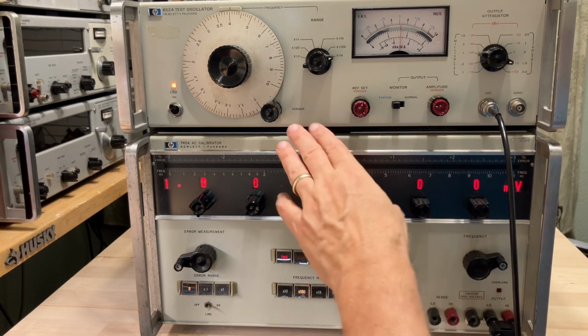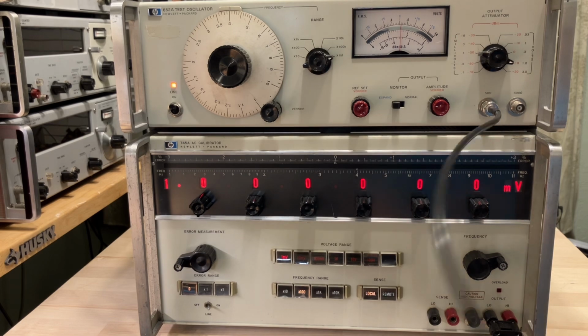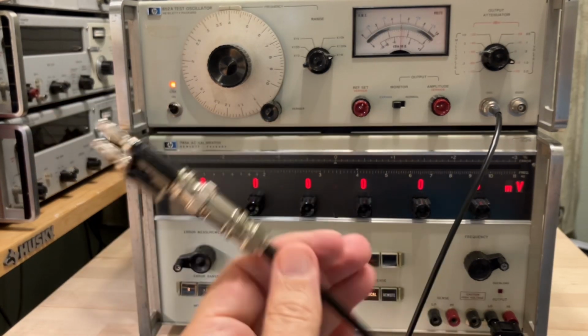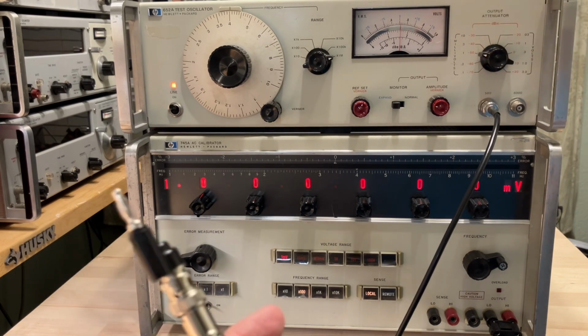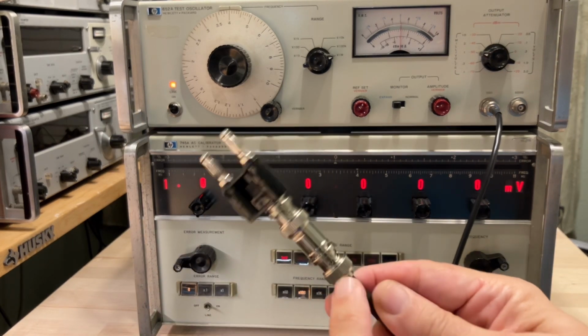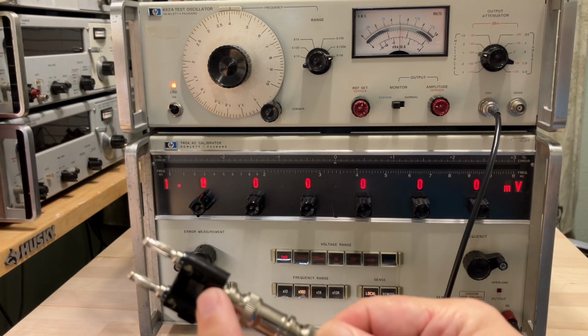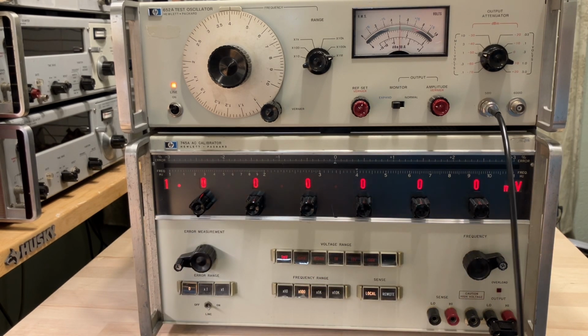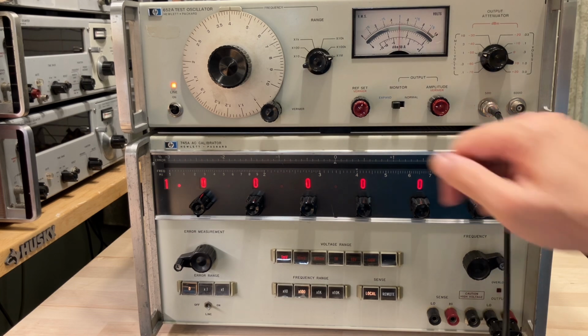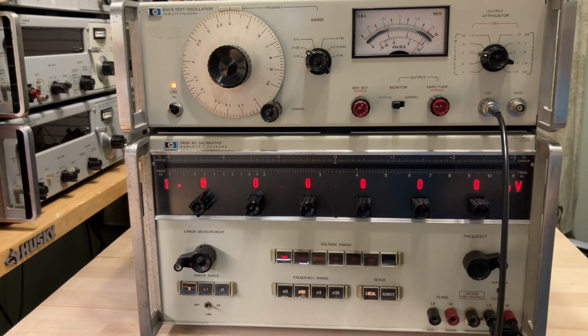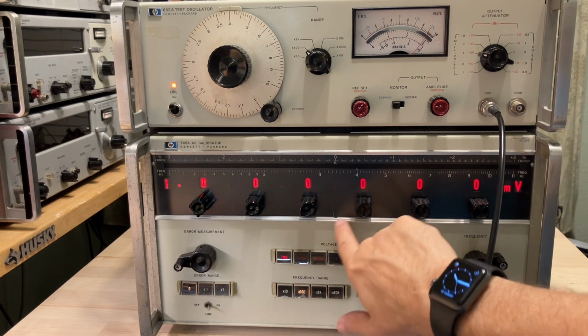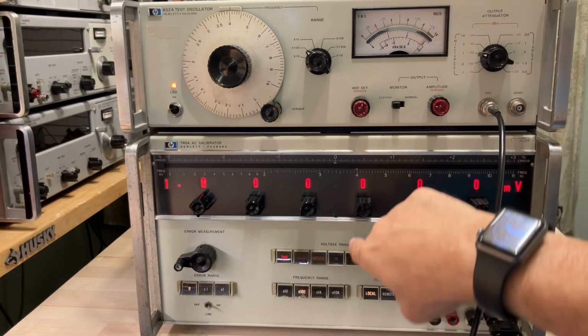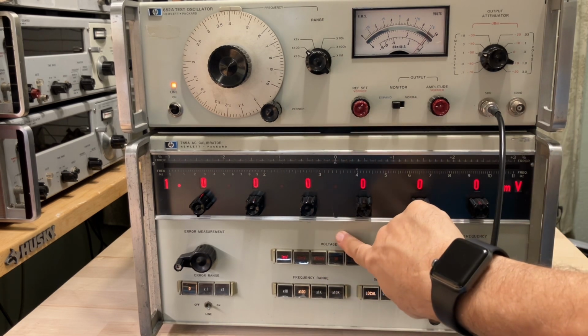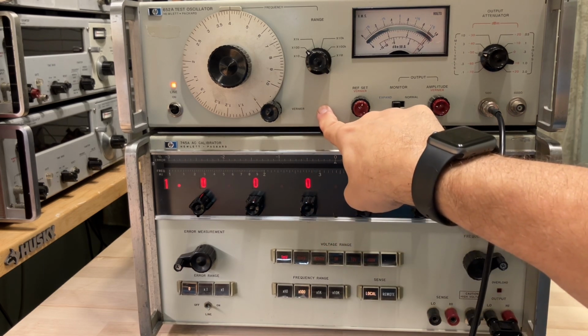Then I take this 652 test oscillator output, which is a BNC cable. I'm going to set it to 1 millivolt also. The BNC cable goes through a 50 ohm termination into a BNC to banana adapter into the input of the 400H voltmeter under test. I set this instrument also to 400 hertz, which it is right now, and I adjust it for the same reading that I had with the 745A, so that the 400 hertz reading from this instrument matches the 400 hertz reading from that instrument.